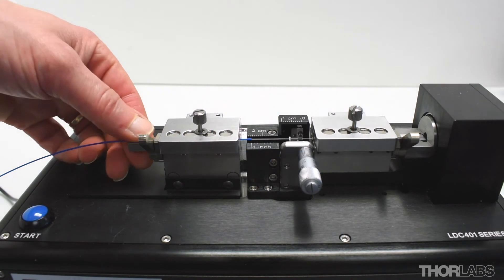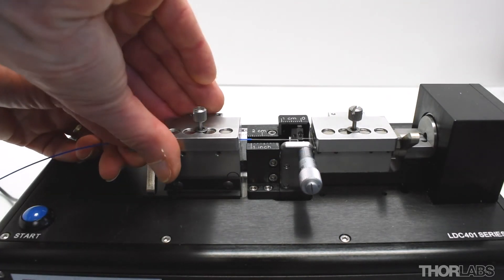To remove the cleaved fiber, press down on the left cam lever and fully open the lid.